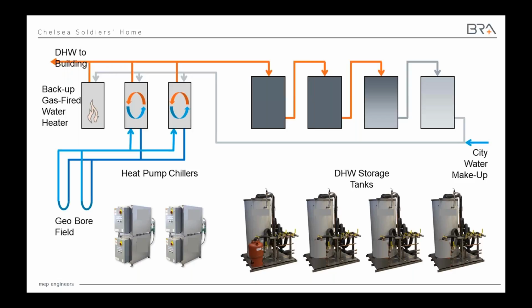So you could either put in a whole arsenal of heat pump chillers that connect from the ground loop into your domestic hot water loop, which is a very expensive approach, or you could put in a couple of modules like you see here on the left, and on the right, put in a series of thermal storage tanks, domestic hot water tanks that you can charge up and then discharge almost like a thermal battery. And then if you have a peak load, you can run both water from the tanks and from the heat pumps to boost it. And that generally will keep the boiler, the backup boiler, from kicking on at all.